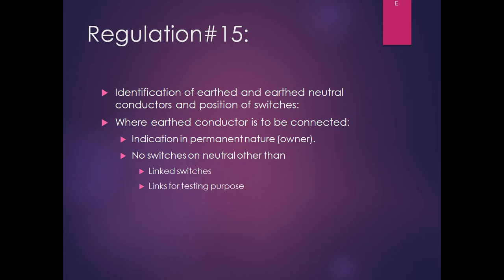Regulation 15 talks about the identification of earth and earth neutral conductor and positions of switches. Where an earth conductor is to be connected, an indication of permanent nature shall be provided by the owner. You can see in the panels also that the location of earth is distinctly marked. There is a sign for earth connection, it shall be present, and that shall be connected with the earthing mat or earthing pits. The second point is that no switch on the neutral other than linked switches or link for testing purpose. Linked switches are nothing but DP switches or 3-pole neutral switches.